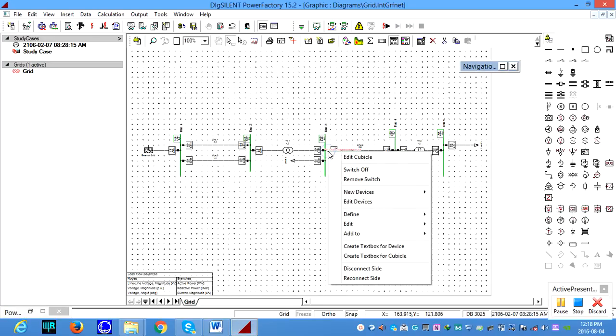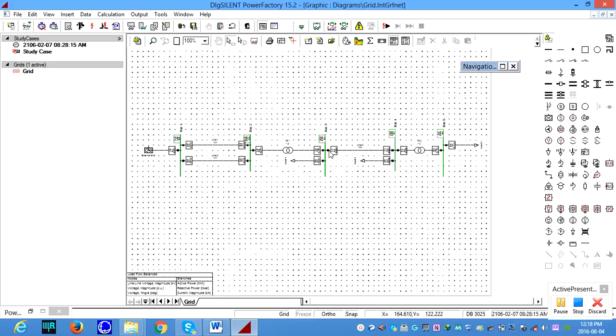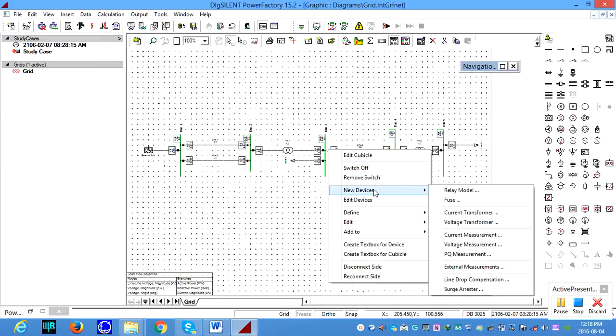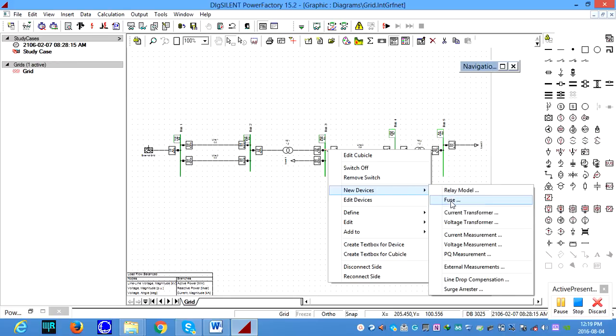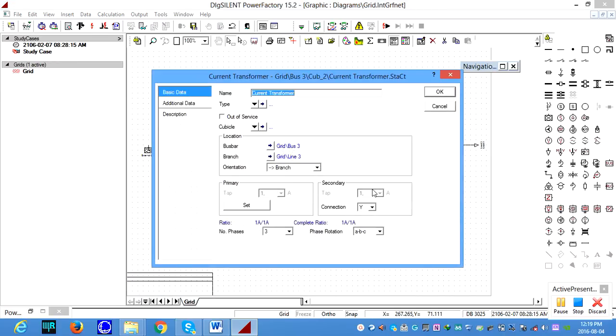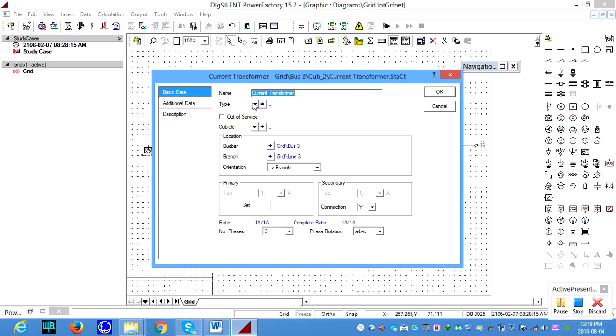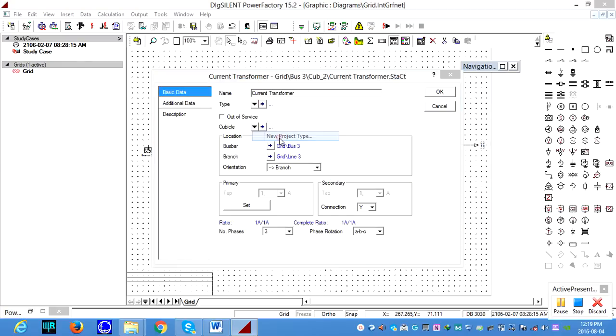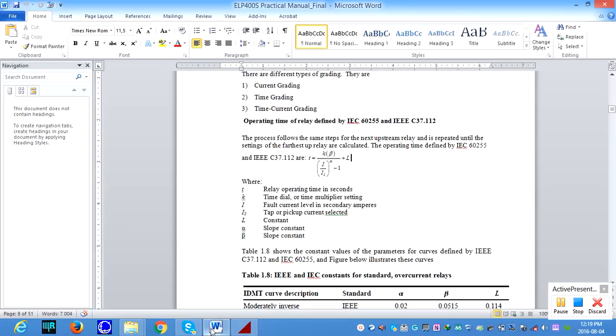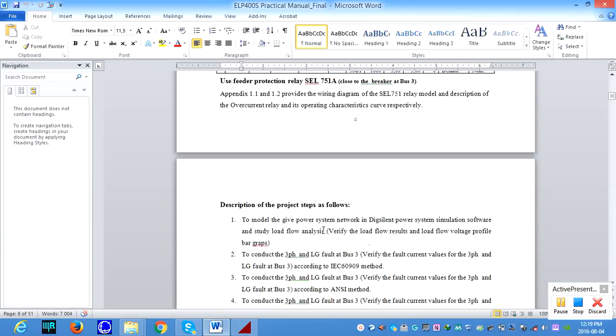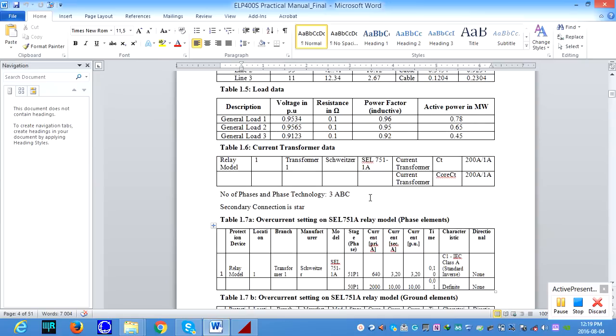And we include, I think you can left click the breaker which is close to this breaker. Okay, I think you need to right click the breaker and go to devices, and first we need to use the current transformer. So select the current transformer, and then there are different parameters that you need to enter for the instrument transformers, especially for the CT. The best thing, you go for a new project type, and according to our data, your current transformer data is going to be 200:1 amps, and number of phases, phase technology 3 ABC, and the connection is star.